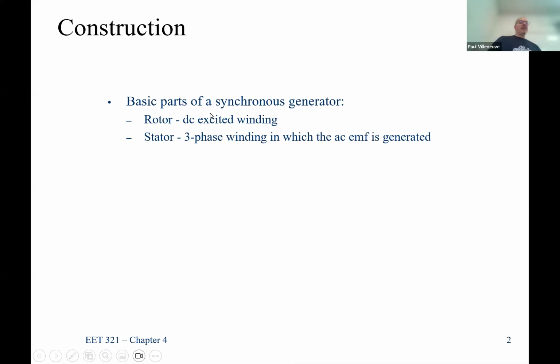And this is the key thing. This has to be a DC winding because we want to make sure that operation of our machine is in sync, meaning it rotates at the same speed as the magnetic field that rotates around it. Okay. So to build the rotor over here, you need a plus and a minus to go in. Now, you can use a permanent magnet inside the rotor to do it. But the problem is, as we'll learn, with synchronous machines you can monkey with this DC excited winding to either get reactive power out of the generator or to have it absorb.